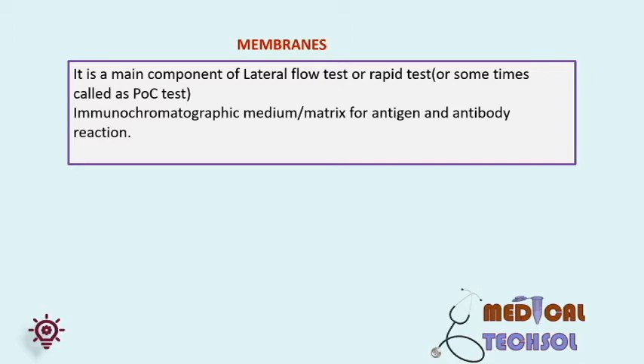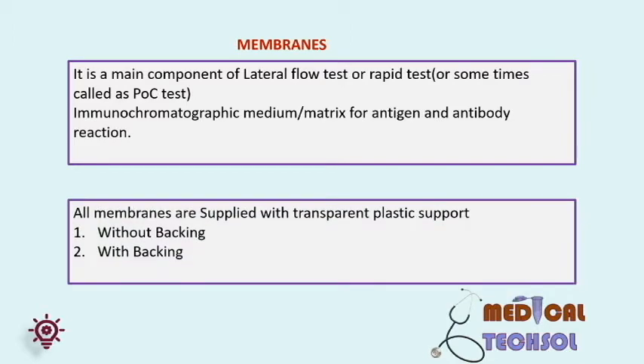Nowadays most membranes are supplied with transparent plastic support. The membranes are cast onto a solid polyester film by the supplier or manufacturer for easy handling and to provide higher mechanical strength, in order to avoid damage during operation or transport. They also separate the membrane from contacting the adhesive or gumming used in the lamination process, thereby acting as a barrier against contamination from adhesive. Generally used membranes are nitrocellulose.